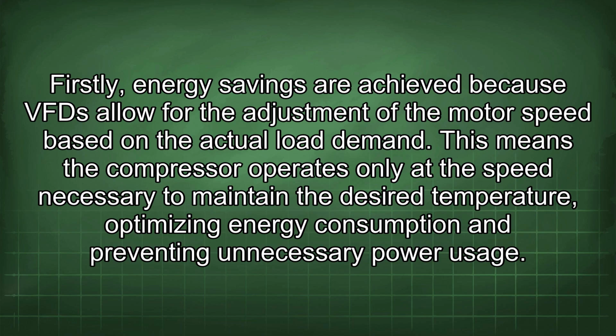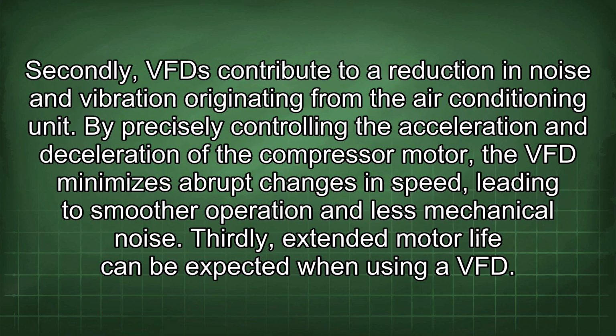Firstly, energy savings are achieved because VFDs allow for the adjustment of the motor's speed based on the actual load demand. This means the compressor operates only at the speed necessary to maintain the desired temperature, optimizing energy consumption and preventing unnecessary power usage. Secondly, VFDs contribute to a reduction in noise and vibration originating from the air conditioning unit. By precisely controlling the acceleration and deceleration of the compressor motor, the VFD minimizes abrupt changes in speed, leading to smoother operation and less mechanical noise.